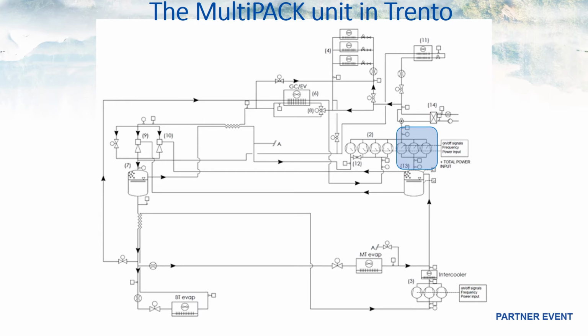This is the unit which is located in Trento. Again, we have a booster system with medium temperature and low temperature compressor racks inside the same circuit. Again, we have the parallel compression, and the expansion is performed by means of two-phase ejectors. The loads are represented by the medium temperature cabinets and the low temperature cabinets.